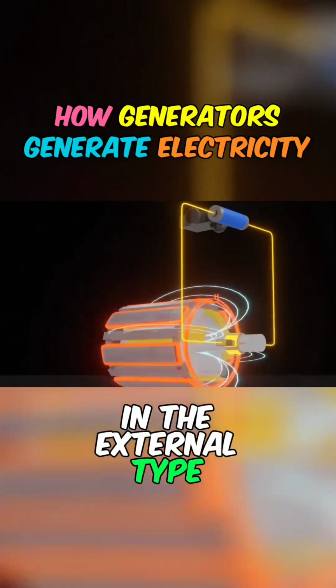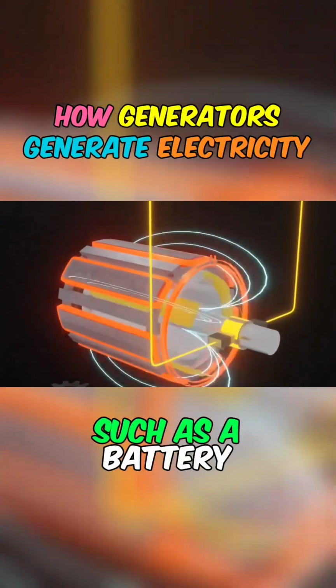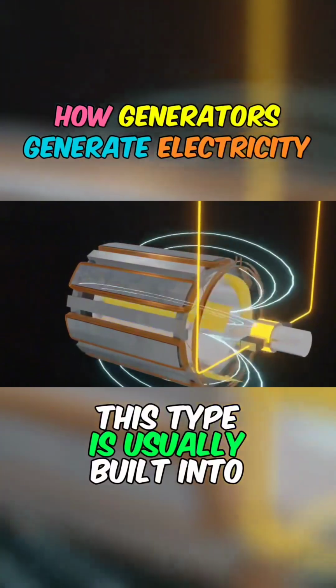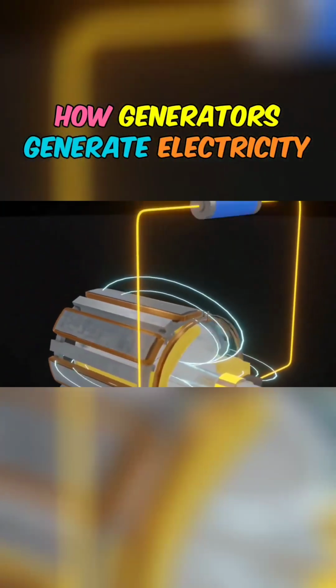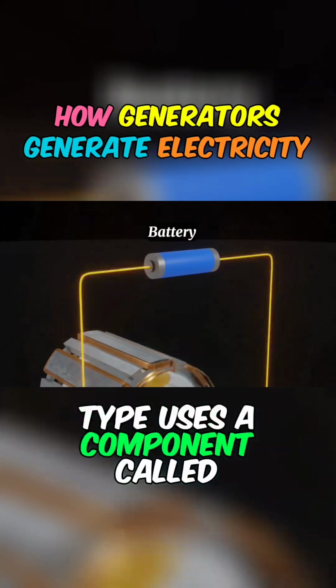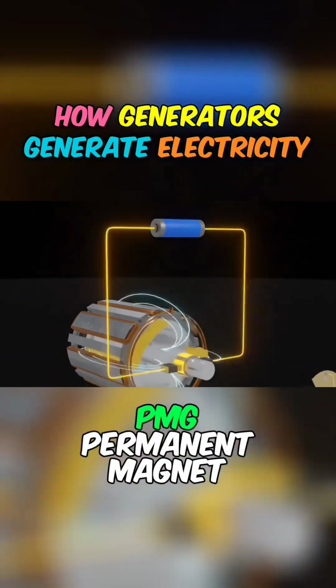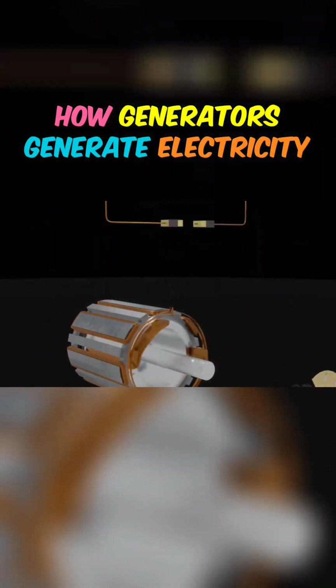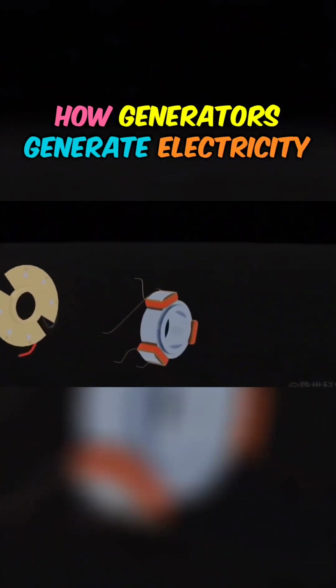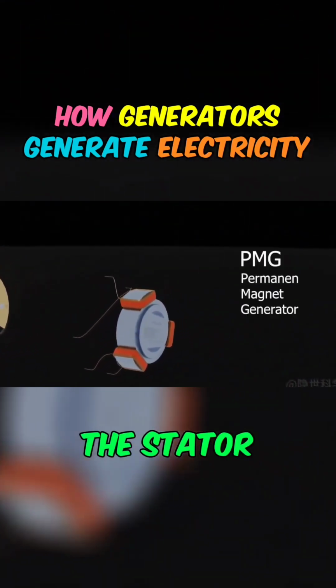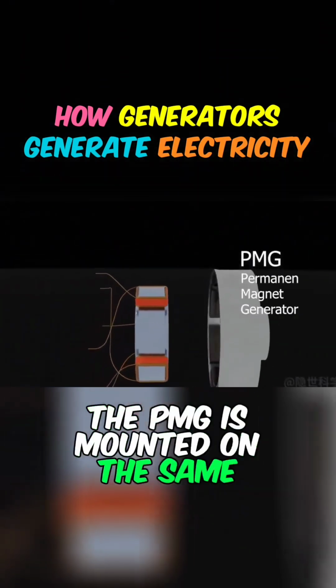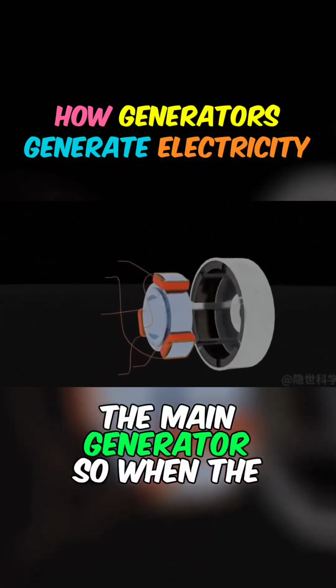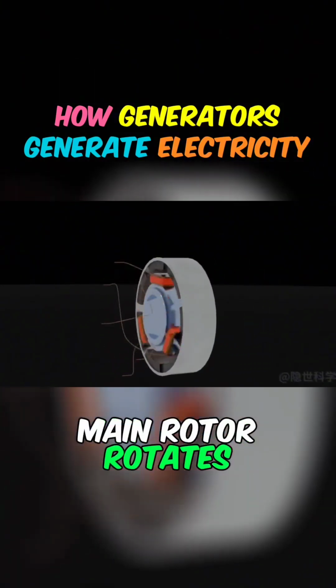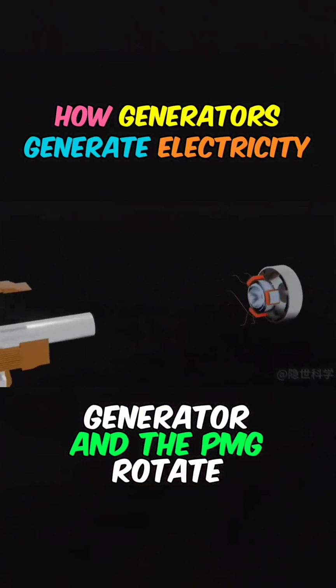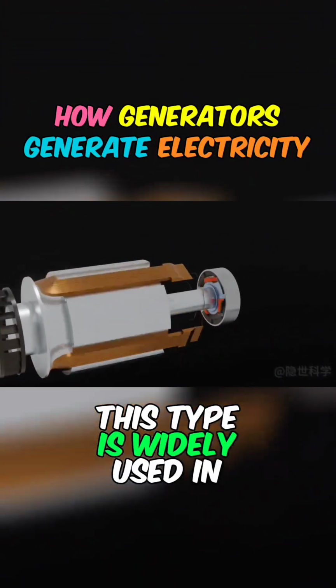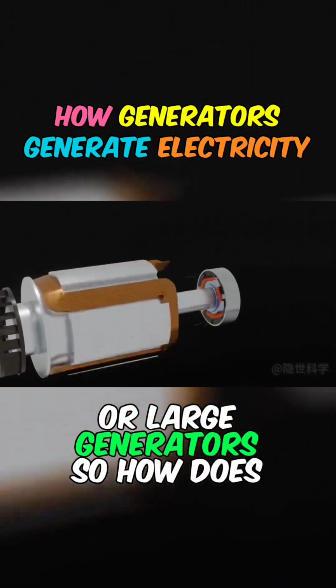In the external type, the current comes from an external source such as a battery. This type is usually built into the alternator on the car. While the self-generated type uses a component called PMG, permanent magnet generator. This is a smaller size generator, but it uses permanent magnets as the stator. The PMG is mounted on the same shaft as the main generator, so when the main rotor rotates, both the rotors of the generator and the PMG rotate. This type is widely used in generator sets or large generators.